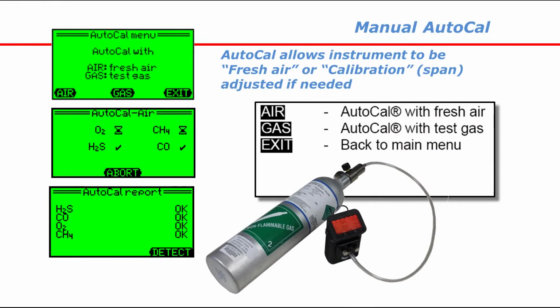G450 instruments are designed to automatically adjust sensor readings during the AutoCal calibration procedure. AutoCal calibration is a two-step procedure. During the air AutoCal step, the sensors are exposed to fresh air, and the readings are automatically adjusted to match fresh air values. In the gas AutoCal step, the sensors are exposed to calibration gas, and the readings are adjusted to match the concentrations in the cylinder of gas that is used to adjust the instrument.